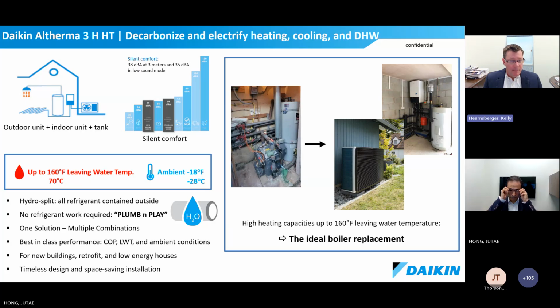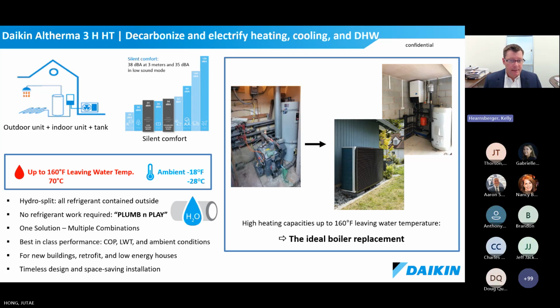So I'll start to describe a little bit about the system now, and then I'll break down even further each individual element. The first question that we get a lot, or the first comment I hear a lot in the hydronics world for heating, is, well, you've got to give me 180 degrees. And that's what typically had been the norm when people thought about boilers and how baseboard or radiators were designed. And we definitely appreciate that comment, but we're also producing a system that is going to replace those with more efficiency, even at lower temperatures. So we're able to reach a phenomenal temperature output on a heat pump, up to 160 degrees Fahrenheit leaving water temperature.